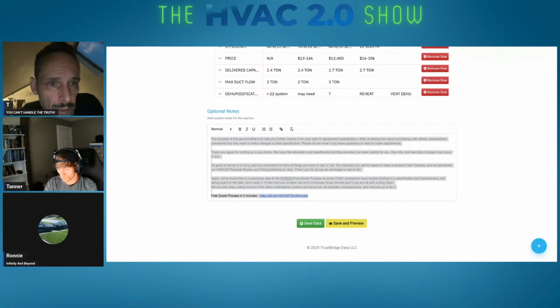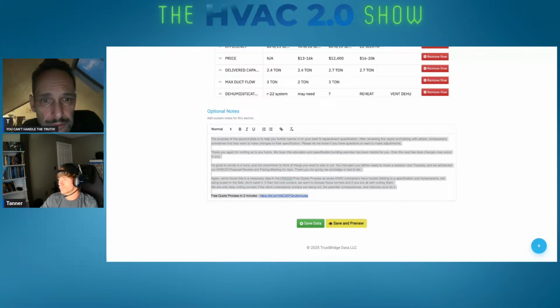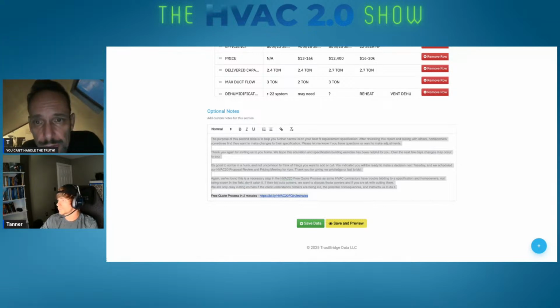That's the standard wording, so that's not modifiable. And this is the modifiable part under that module. If you want to replace your current equipment with the same size single stage equipment, please remember the new equipment does not operate the same way the old equipment operates. We find homeowners have the best results when the new equipment's static pressure is just above 0.4 on the high stage. To achieve this for your house, we need to either replace with smaller equipment or increase the size of some or all of your ductwork.